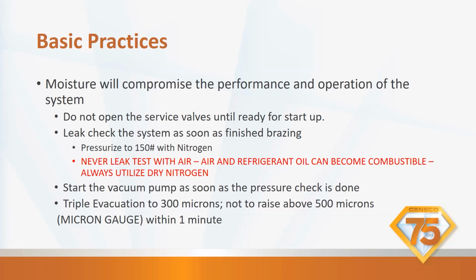Using the triple evacuation, what it actually does is our vacuum pumps are so efficient now that as they pull down, they'll freeze the moisture inside the pipes. So by doing a triple evacuation, and what that means is pumping it down to about 1500 microns, bring it back to 0 with nitrogen, pump it down again, down to about 1000 microns. And then if it's coming down nice and steady, you don't need to do it more than once. But if it's not coming down as fast as you think it should, do it again at 1000, and then go down to 300 microns. Okay, shut the system off, shut your gauges off, and it should not rise above 500 microns within a minute. If it does, you either have a leak or you have moisture.